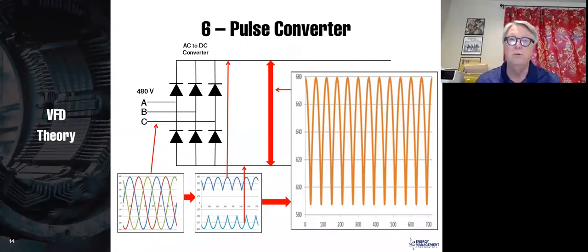These diodes are simply check valves. They let current flow in one direction. Which direction? Well, the direction of the arrow. So whenever A phase is most positive, then that check valve will open up and it will let current flow through A phase. When A phase begins to go down and B phase becomes the most positive, then the B phase check valve will open up and the current will then flow onto the DC bus. The same happens on the negative side. So we get this three-phase, and basically what it's doing is letting the most positive portions of the AC wave through to the positive DC bus, and the most negative portions of the AC wave go through and end up on the negative bus.